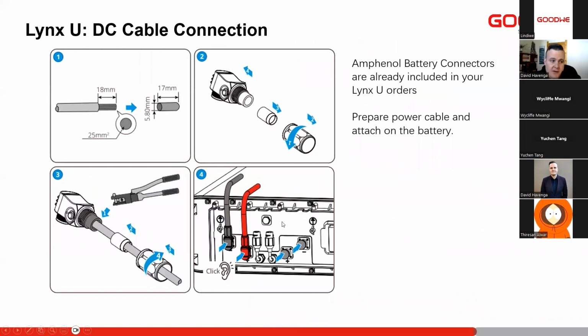Then our Lynx U batteries. With the batteries, we include these connectors. The Amphenol battery connectors are included. They do not have pre-made cables on them. Essentially, you'll insert the cables. There are 2 grommets for different sizes, one for a 20 mil and one for the 35 mil. We need to make sure we install the right cable with the right grommet and crimp it with a proper crimping tool. And always make sure to hear the click when we install them.